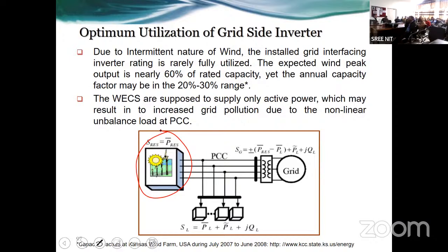At that time they were also having issues with the conventional wind power plants, because in North America, especially in the upper region of Quebec, they have squirrel cage induction generator based wind turbines. Those SCIGs draw more reactive power, and that reactive power needs to be fed by the grid if there is no converter. So they were looking for a study on retrofitting, where those SCIGs could be replaced with PMSG based wind turbines, where a full-fledged power converter topology is there, and the power converter can also be utilized for reactive power compensation of nearby SCIG or load or something else.